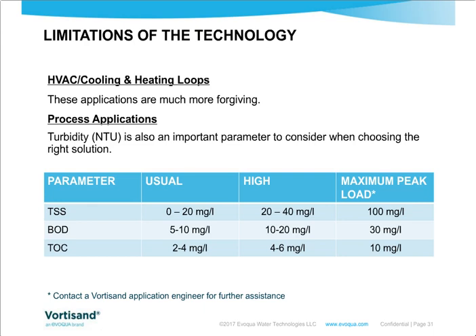Now, I've talked to you today about how fine filtration is important for HVAC and for different process applications, but it should also be noted what the limitations of high-efficiency fine filtration are. In HVAC cooling, your TSS and turbidity levels are much different than in your process applications. It's important to understand the differences. For the Vortisand fine filtration, in terms of TSS, BOD, and TOC, there are a number of different boundary limits, or basically peak loads, associated with each of these parameters.